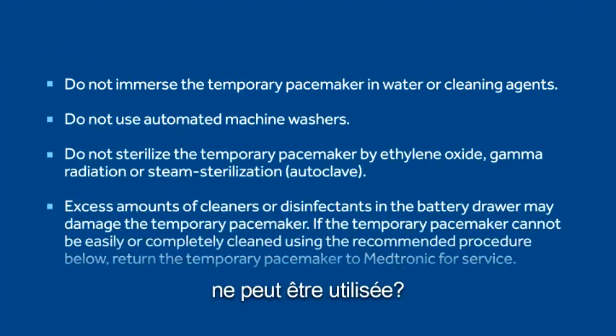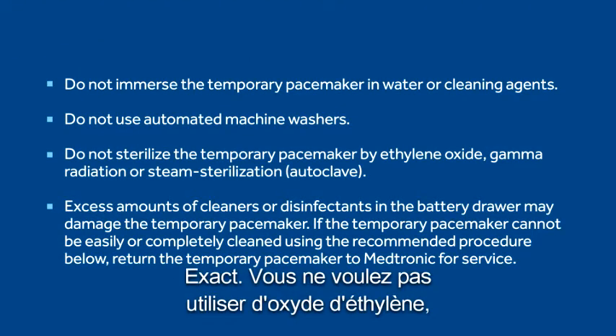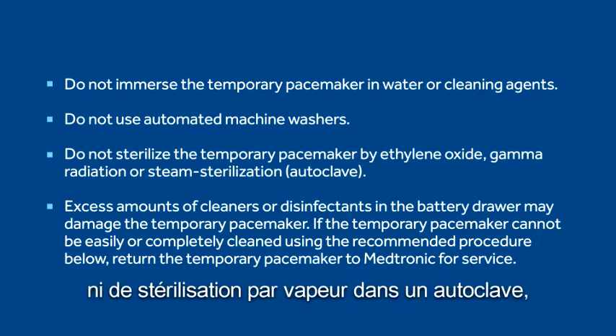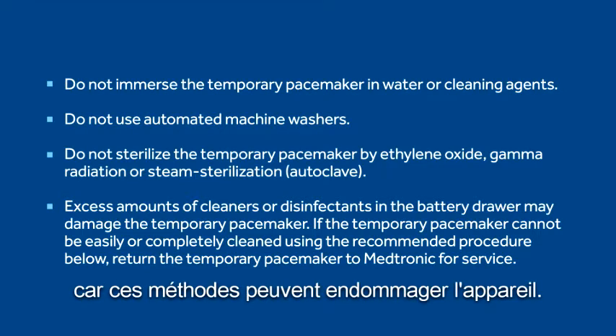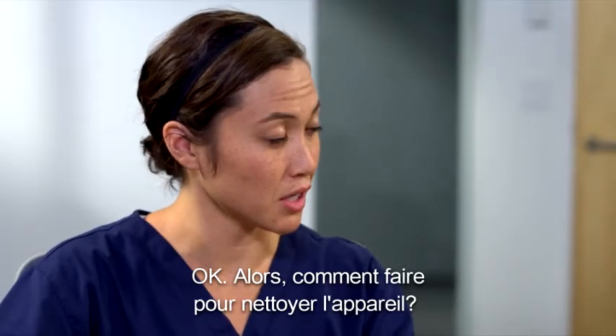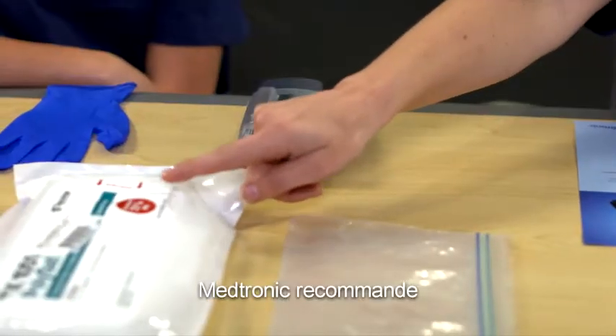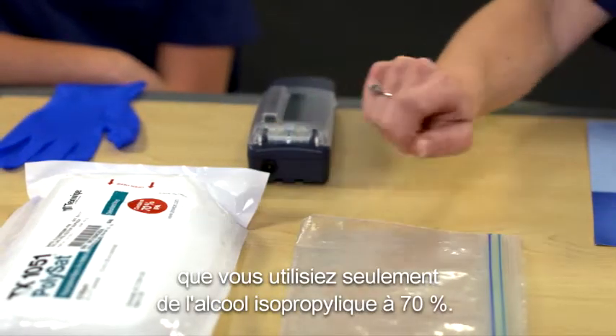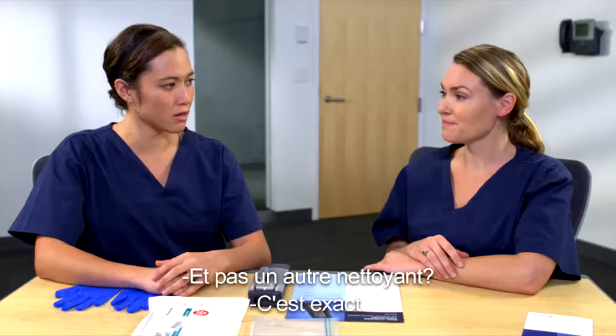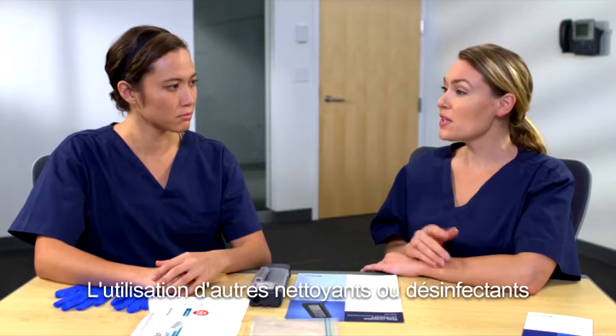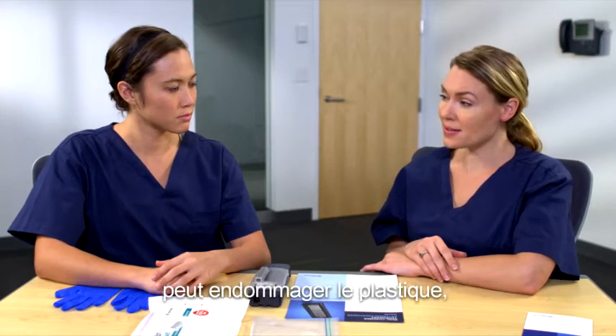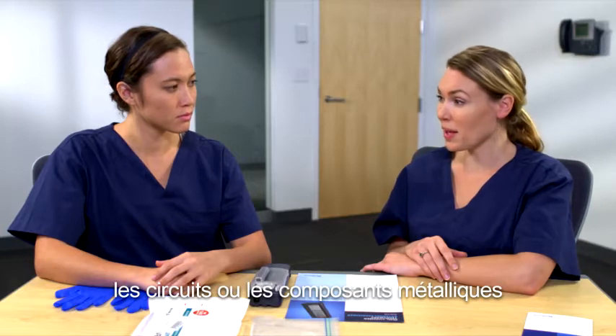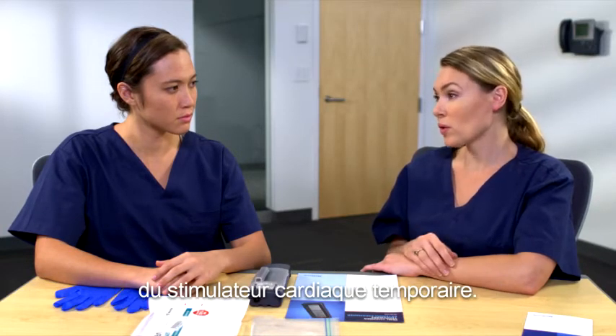Great, so none of the automated machine washers can be used? Correct. You don't want to use ethylene oxide, gamma radiation, or steam sterilization in an autoclave because it can damage the device. Okay, so what should I do to clean the device? Medtronic recommends you use only 70% isopropyl alcohol. Really? Not another cleaner? That's right. Using other cleaners and disinfectants may cause damage to the temporary pacemaker plastic, circuitry, or metal components.